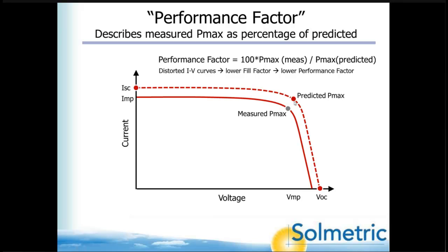And if we divide the measured maximum power, located at the gray dot, by the predicted max power, which is located at the red dot, and multiply that by 100 to convert it to a percentage, we get the performance factor. And that is the primary metric that we use in the PV analyzer to express whether it's a good string or a bad string, or whether there are problems in it. And the fill factor that I mentioned earlier is a very helpful troubleshooting tool as well.